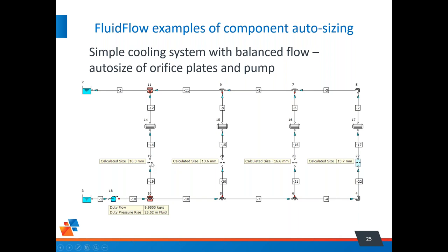We're applying some orifices at a calculated mass flow, and the software will generate the size of the orifice to ensure that we have balanced flow through them. On top of that, we ensure that the flow is through a pump, and that duty flow and duty pressure are calculated from the auto size. So that allows us to go back and look at, say, a manufacturer's catalog and find a suitable pump for that system.